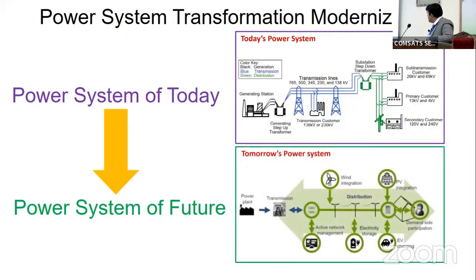So the future grid will be bidirectional. Right now our transmission system is reinforced and bidirectional, in a ring or mesh configuration, but our distribution system is not - it's mostly radial. So if you have to convert a system to an interconnected one, you have to improve or upgrade the protection system. Then the classic impedance protection and similar methods will become history if you move towards numerical protection and other approaches.